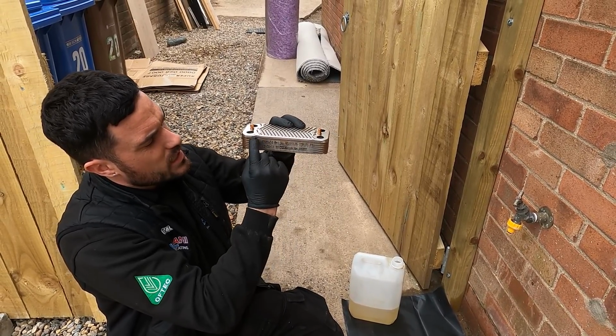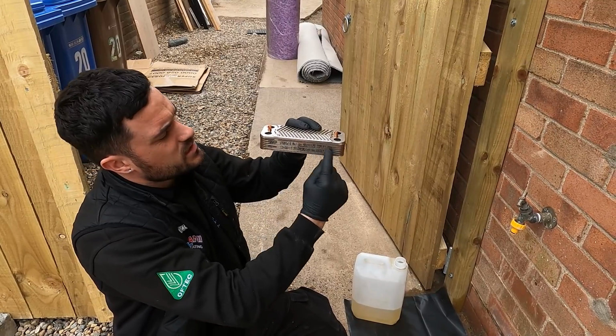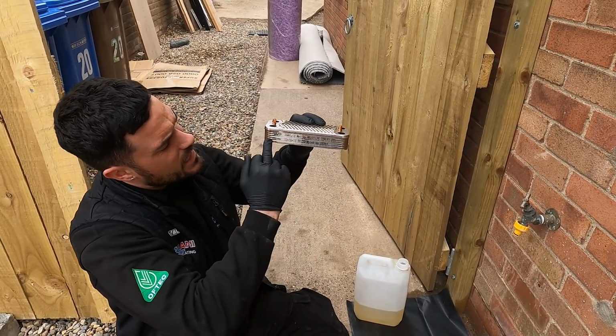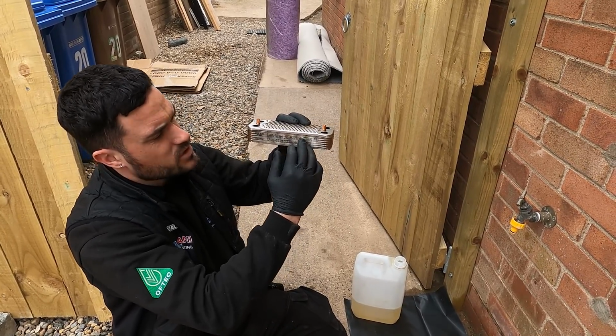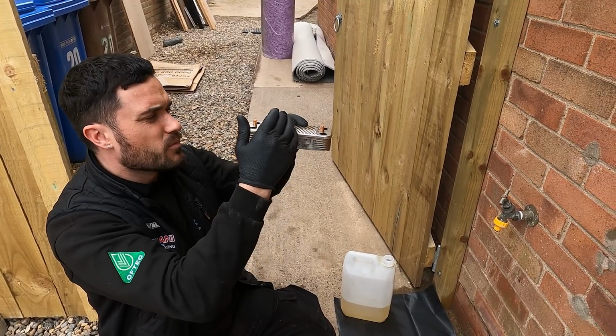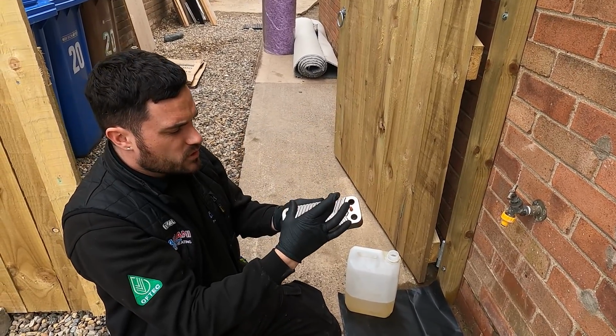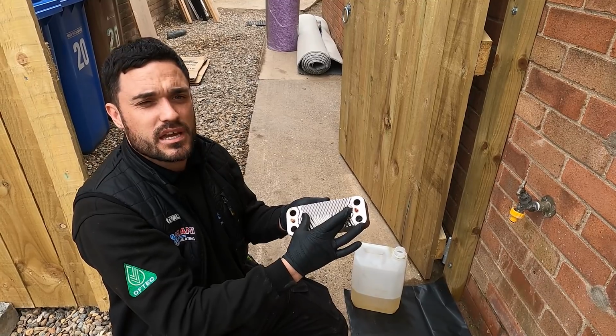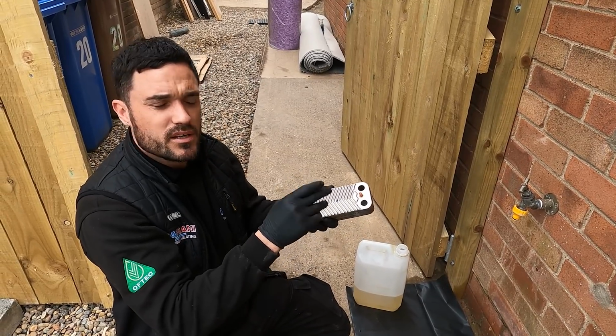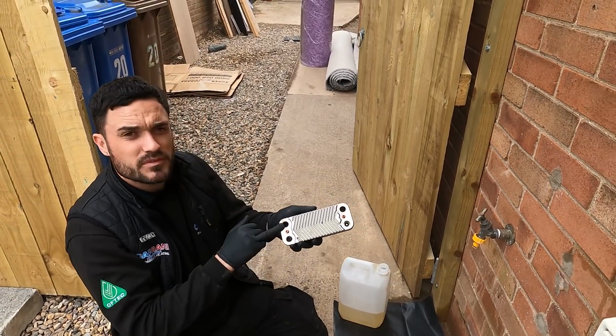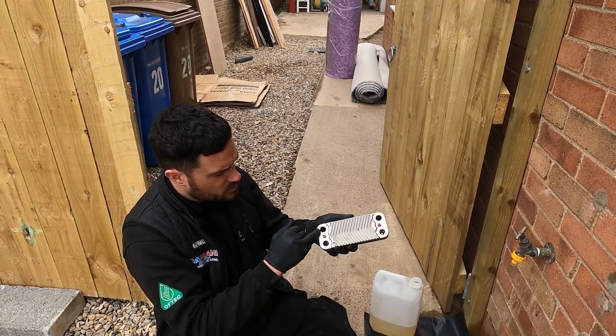So you'll have cold water, heating water, cold water, heating water, cold water, heating water. As it gets to the bottom and comes back out, it's hot because it's created heat transfer from the heating supply, as the water from the boiler's main heat exchanger never mixes with the cold water. So this is how it works, but you can see inside when we've taken it out how dirty it is and how much debris is inside.